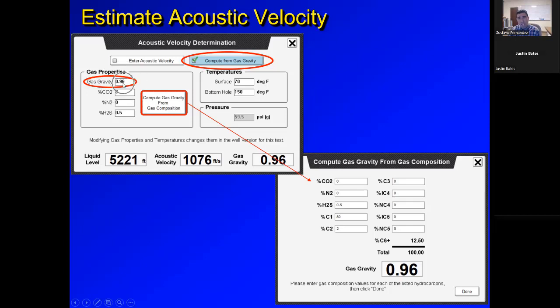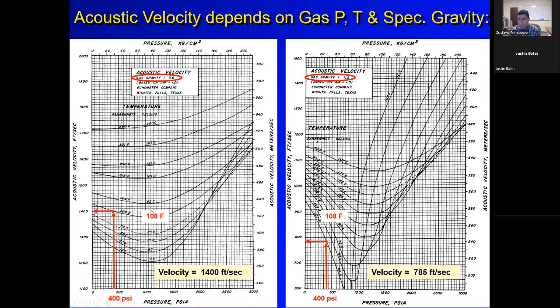And it's very sensitive to the gas gravity. So you don't want to guess the gas gravity. Also, you don't want to use a gas sample taken from the sales point or after the separator to calculate the gas gravity, because that gas composition is not the same as the gas composition in your well. It's important that, if you're using the gas gravity, it should come from a sample from the wellhead, not down the road in the facilities. The software will use that information, based on the gas gravity, pressure, and temperature of those lines, to calculate the resulting acoustic velocity.